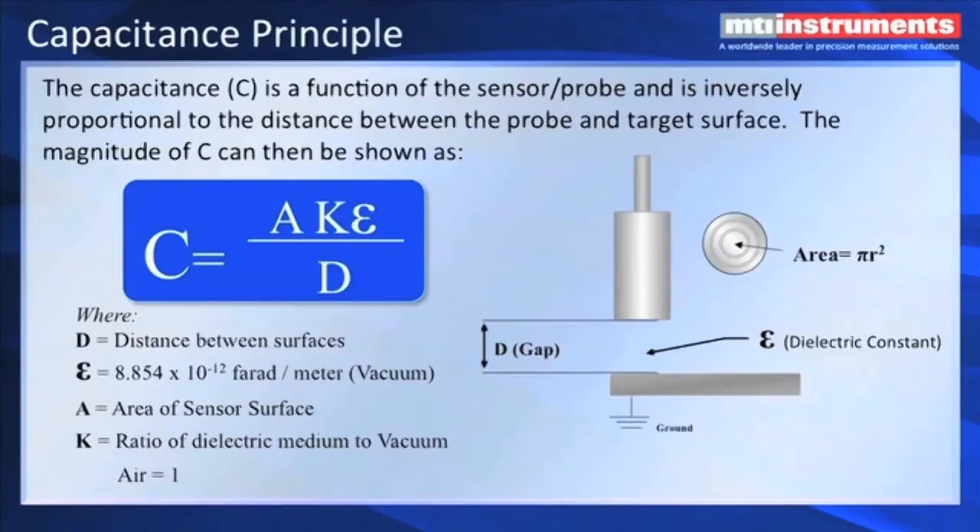We also have very low temperature and time drift electronics, and we can achieve 0.02% linearity or better. A little of the science behind the capacitance measuring principle: capacitance is equal to the area of the probe times the ratio of the dielectric constant of the medium, which is typically air, to vacuum. In vacuum, it would be 8.854 picofarads per meter. Typically the difference between air and vacuum is one-to-one for all practical purposes. We also have the distance — the gap from the face of the probe. As that gap increases, the capacitance is obviously going to get smaller. If we increase the area of the probe, the capacitance is going to go up. So it's a trade-off between the gap you want to measure and the size of the probe.